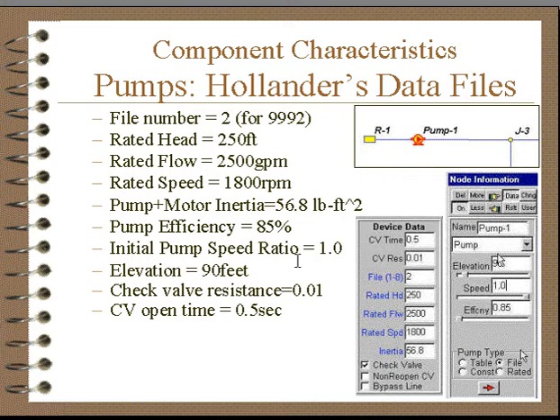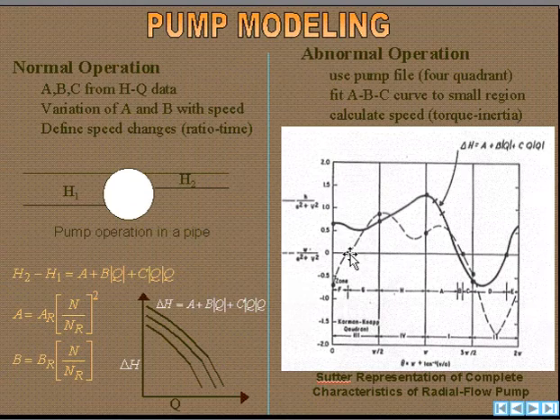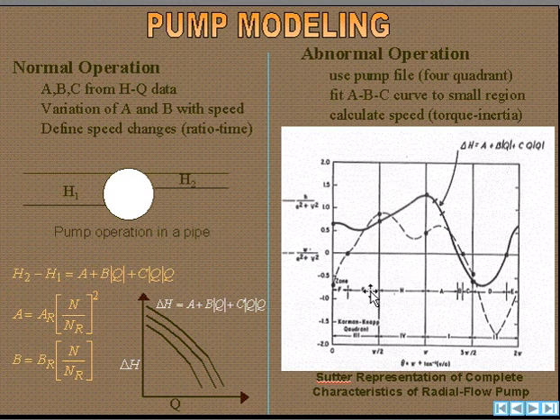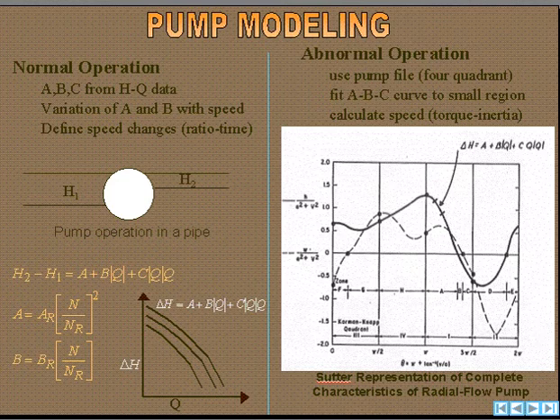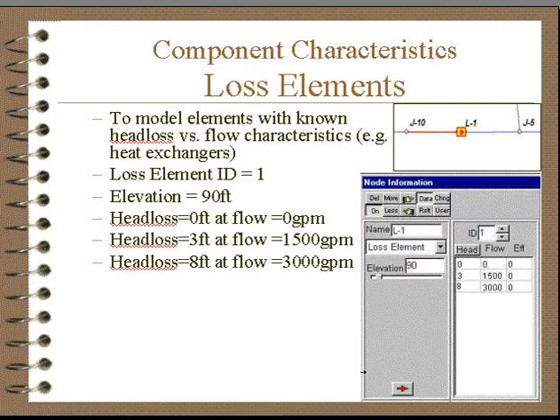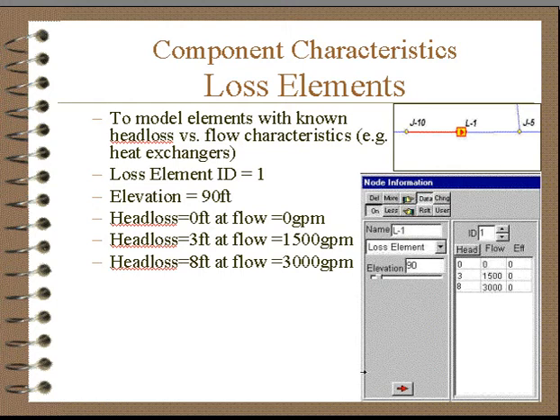The difference with this pump type is that it uses dynamic characteristics which give you torque and head versus speed and flow. We can calculate the rundown time, so we can actually look at what happens when the power fails to the pump and the pump trips. Loss elements can also be handled in transient flow, and the loss will be based on the curve described by this data.